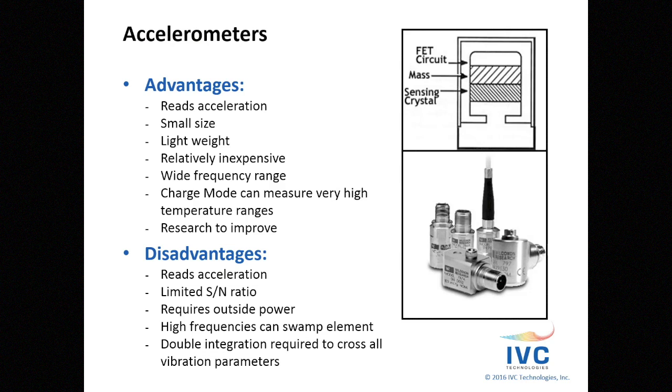Some of the disadvantages: it reads acceleration, and that's an issue if you want another unit like velocity or displacement. There can be a limited signal-to-noise ratio. They require outside power. High frequencies can swamp the actual internal sensing elements. And double integration is required to cross all vibration parameters, i.e. get from acceleration to displacement.